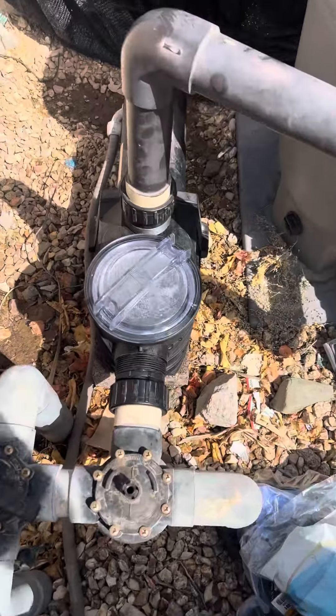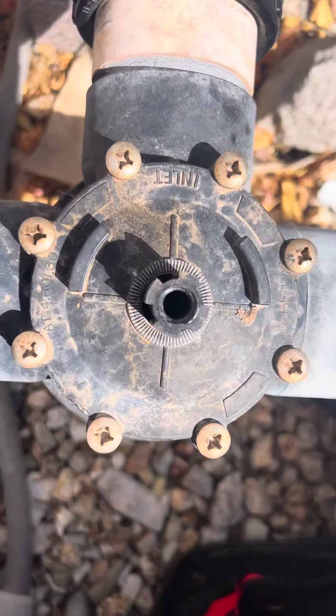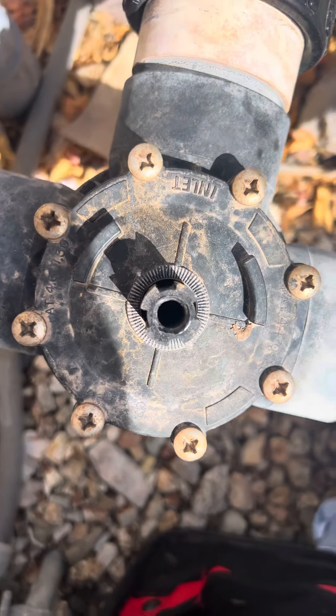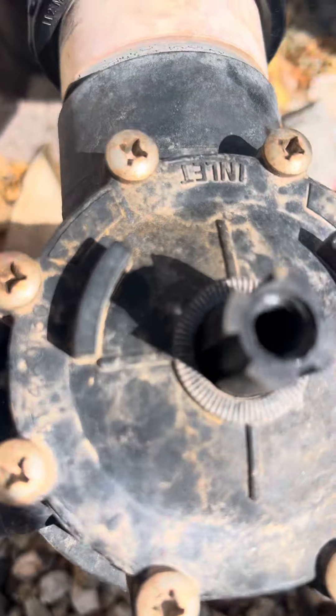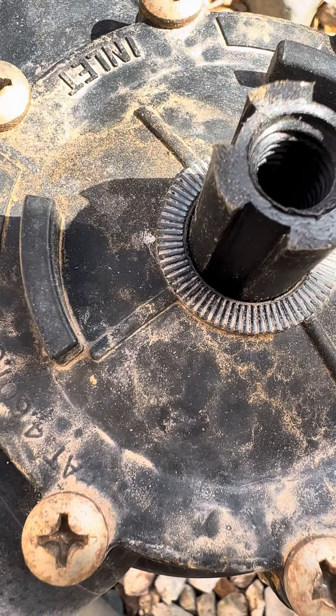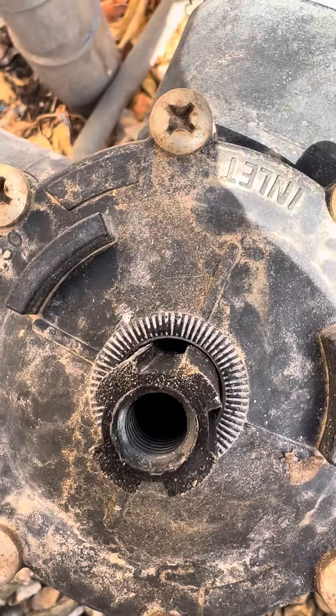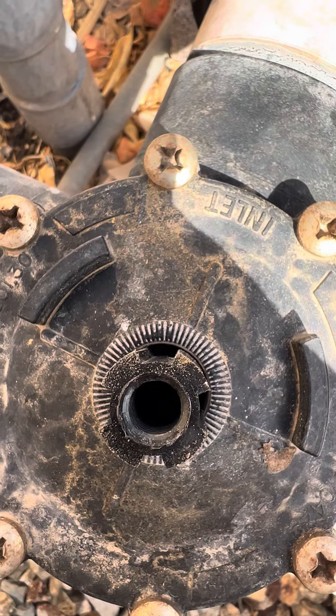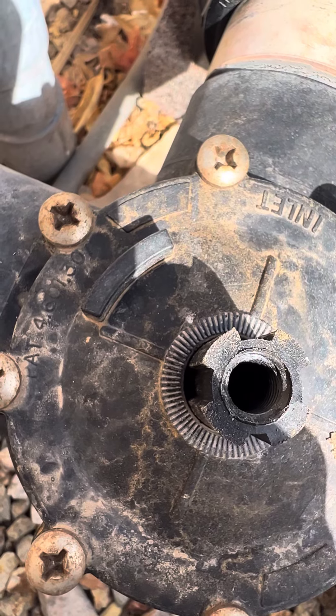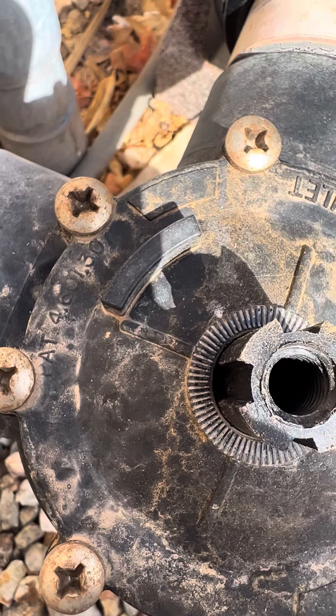So one thing I did is watch when I shut the pump off — watch this valve. It's hard to see it in the video but water's coming up. You can hear it. Water's squirting up. That little bit of suction leak there — you see that?